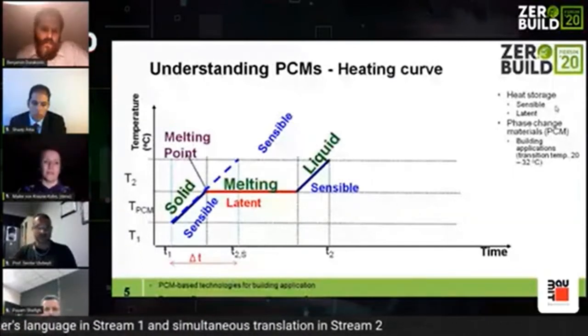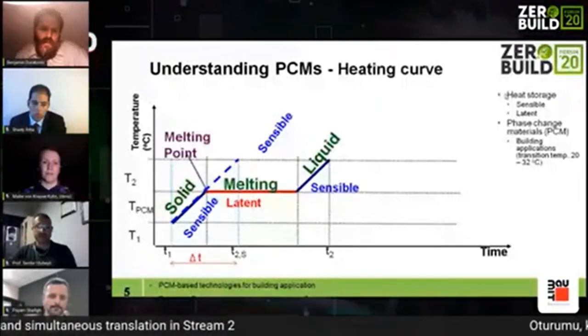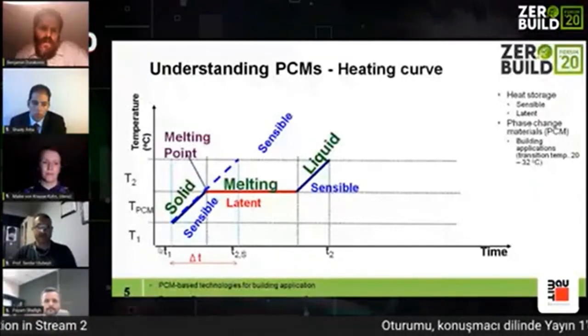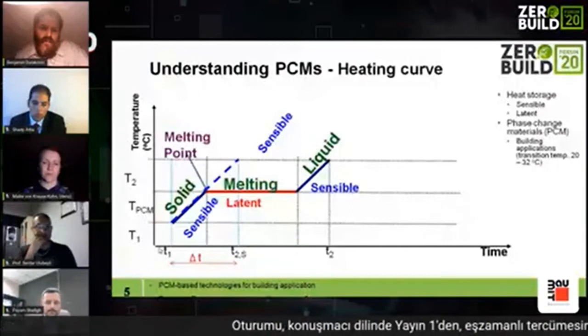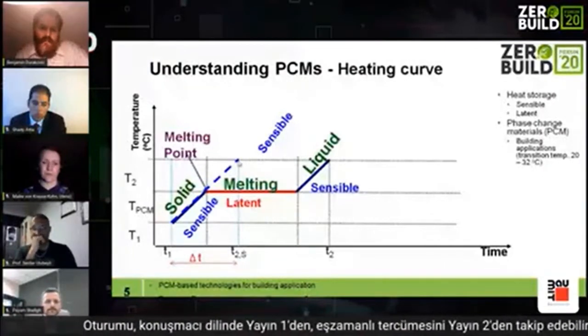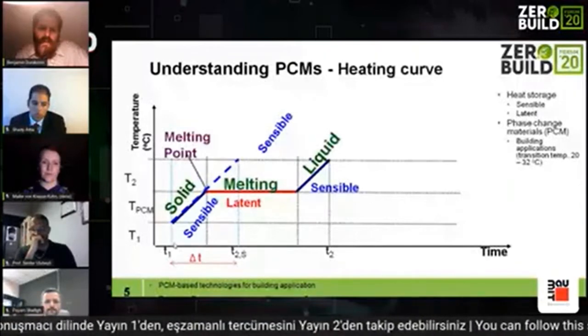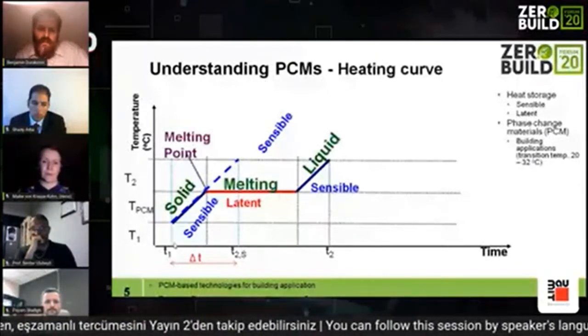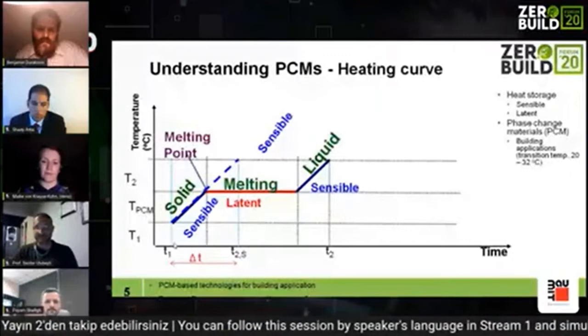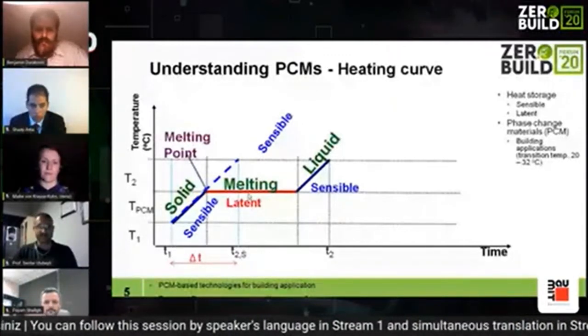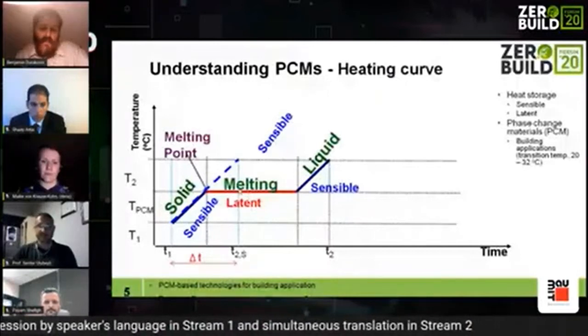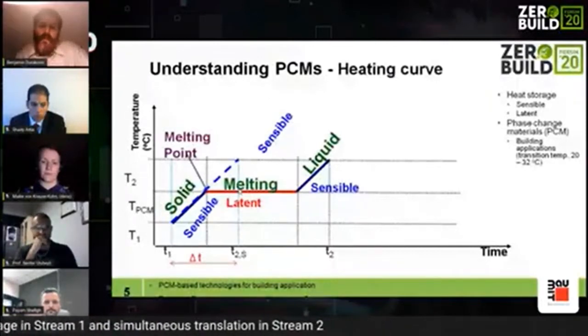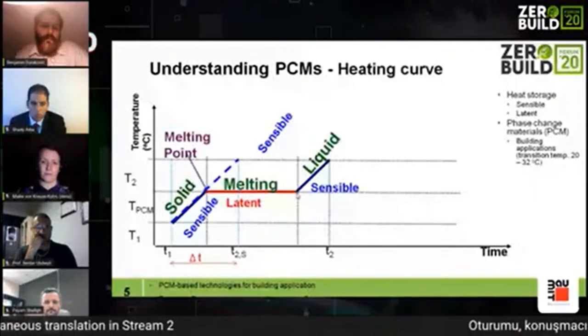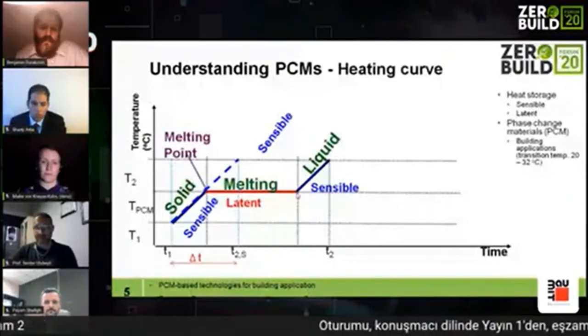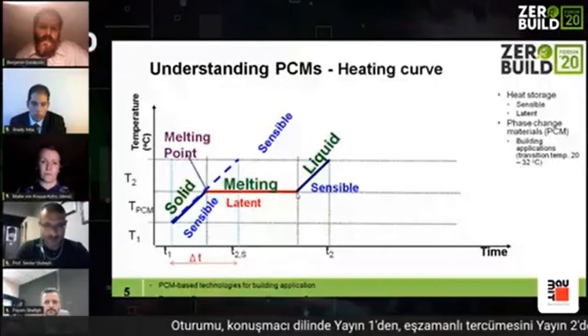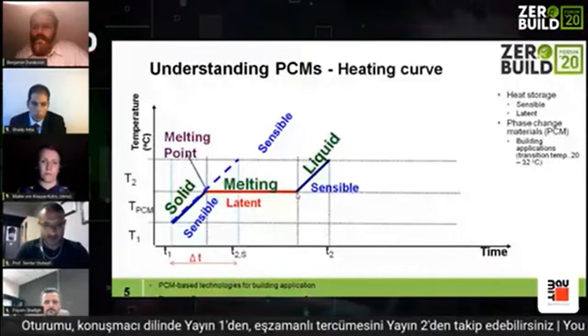In the first case, the area under the curve represents sensible heat. But with the PCM material, the area under this red line is considered the latent heat. If the ice is melted completely and we continue heating the water from temperature 2 to temperature 3, the area under that curve is considered the sensible heat of the water.